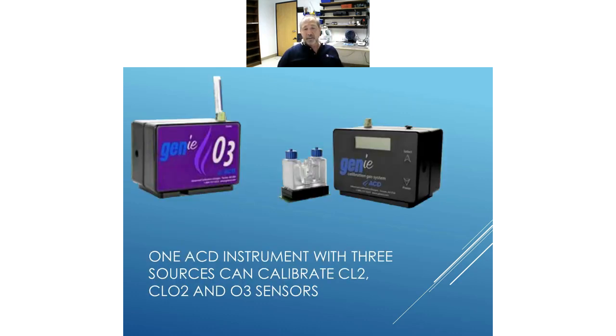So as I mentioned, here is what one of our instruments looks like. This is a Genie. The small cell is what a chlorine or a chlorine dioxide electrochemical cell looks like, and then on the left, that ozone module is what the ozone source looks like. So this one instrument, we show you the front and the back of it and the source. You can use that one instrument to calibrate chlorine, chlorine dioxide, and ozone if you have all three of those.